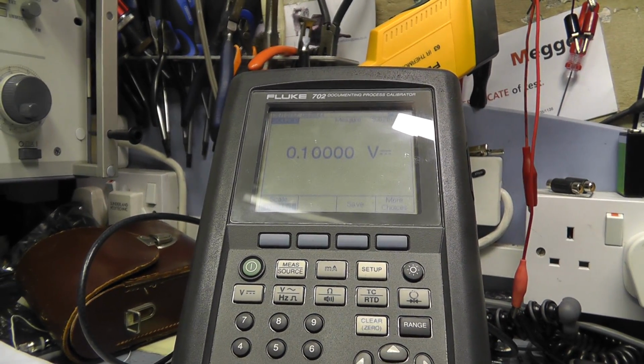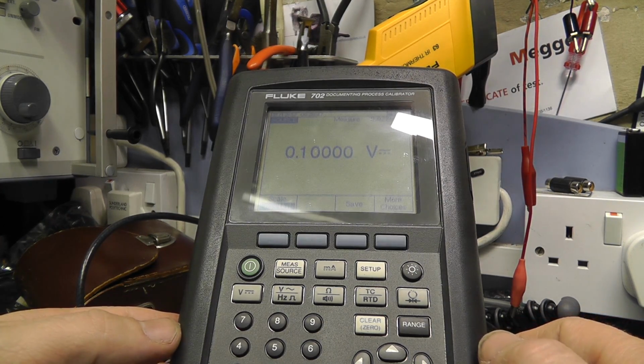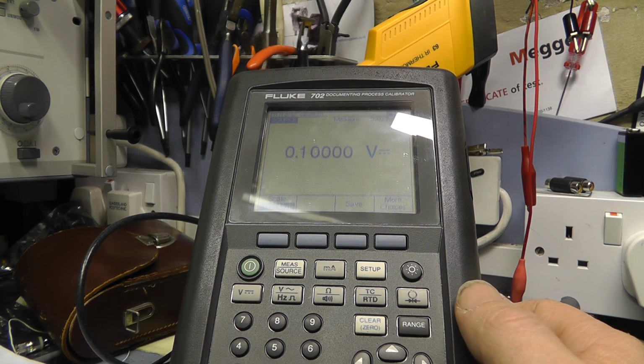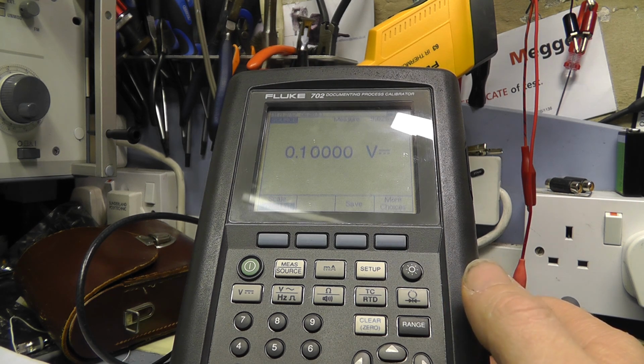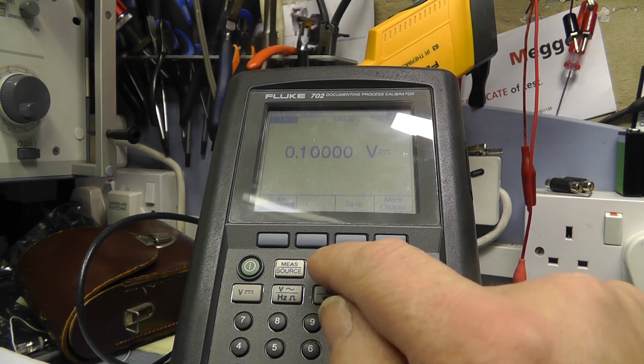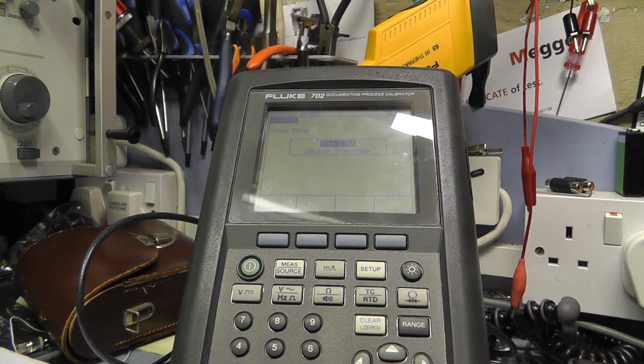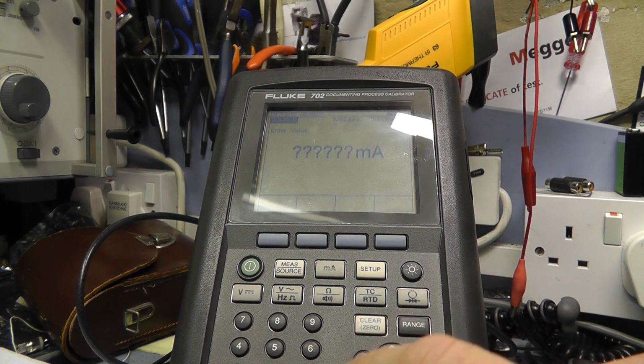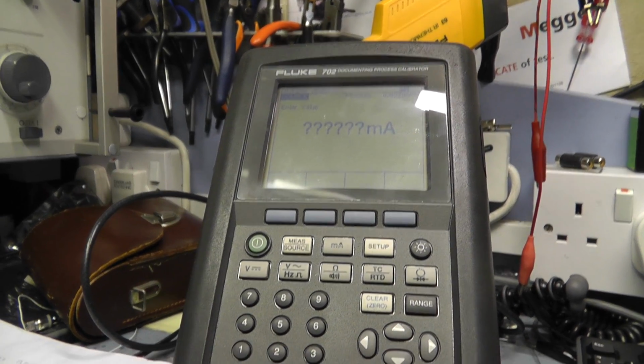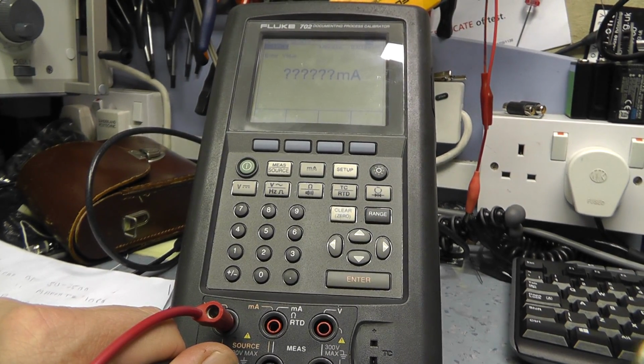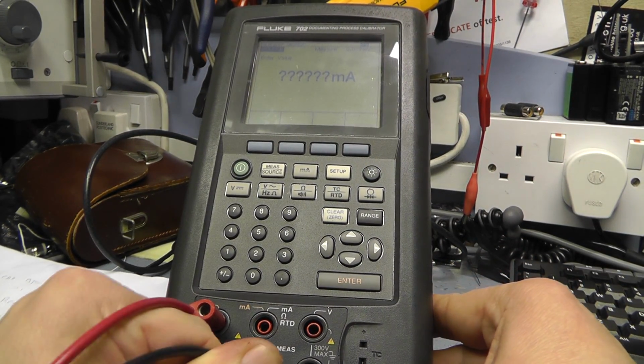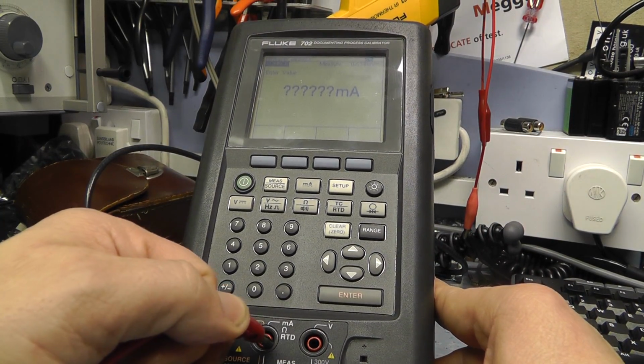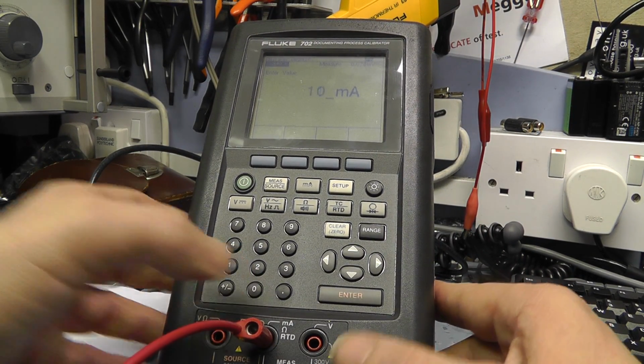To select current mode, obviously I need to change the leads, and last time I tried it's a bit of a fiddle, but first of all I'm just swapping the leads at the moment over on the Solartron and selecting the current reading. Then all I do is press milliamps, and I want source milliamps - this is for simulating transmitters, things like thermocouples, which we're not interested in at the moment. Press enter, and then it will ask you what milliamps you want. I'm swapping my leads over to the milliamp input, because this is where the milliamps is sourced. We'll start with, say, 10 milliamps - 10, enter.